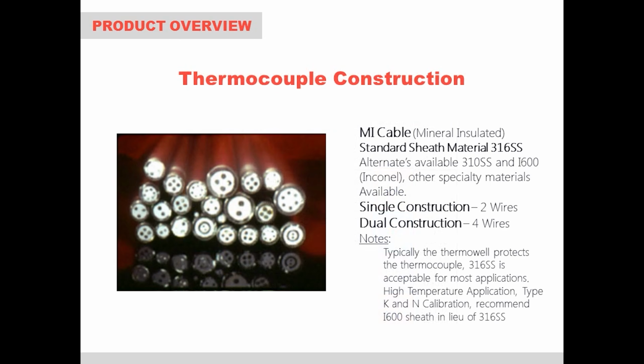Quality and rugged thermocouples start with mineral insulated cable, or MI cable. This modern construction replaces the traditional exposed thermocouple lead wires separated with ceramic insulators commonly used years ago. Standard sheath construction of this cable comes in a number of ODs, the most common being 3/16 inch, 1/4 inch, and 3/8 inch OD, and in 316 or alloy 600 for higher temperatures. We receive this material in 100-foot coils and have numerous coils of the different thermocouple calibrations, diameters, and materials. The MI cable is cut to length, the junction is made at the one end, and lead wires are made at the other end, referred to as the cold junction.